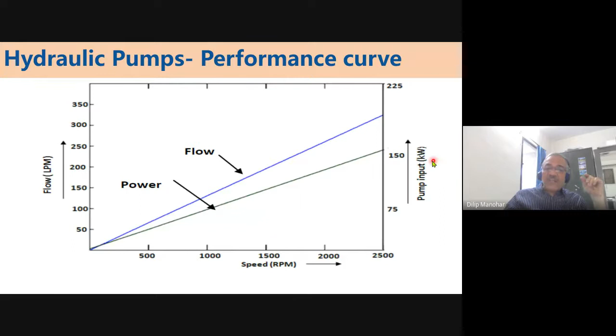Now the positive displacement pump has a constant flow. Sorry, not constant head, I'm sorry. It will develop a constant flow. That means the discharge volume remains constant, so flow per minute is almost constant. In theory it can be slightly reduced at higher head, but for practical purposes we show it as a straight line. In a centrifugal pump, as the flow changes, the head can come down drastically. But here the flow is almost constant as the required head increases. Head is increased, flow is constant.